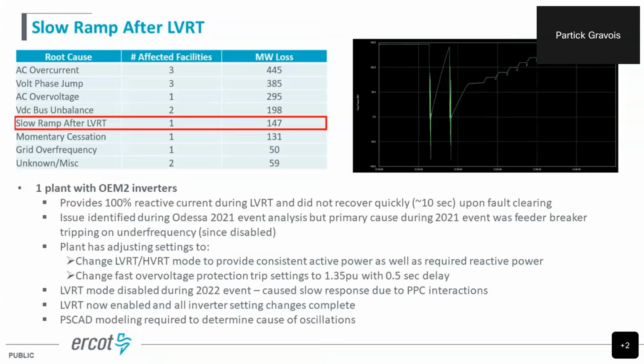Through back and forth with this, we were trying to figure out why they had this slow ramp rate after LVRT, as you can see in that top right graph. And they found out that they actually had LVRT disabled during this event. That's why they had this slow response after voltage recovered. You had some PPC and inverter interactions that made this weird ramp rate and then this odd step function you see as well. So they have now enabled the LVRT, so they're expecting, for one thing, the megawatt would not drop nearly as much as it did in this event, and then it would come back immediately upon fault clearing.